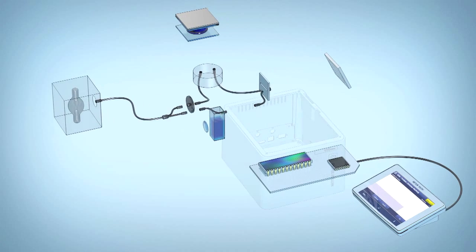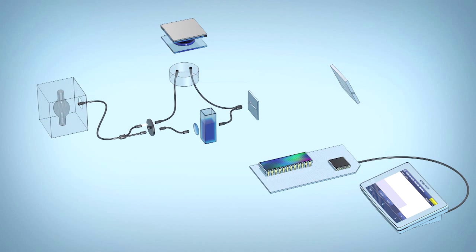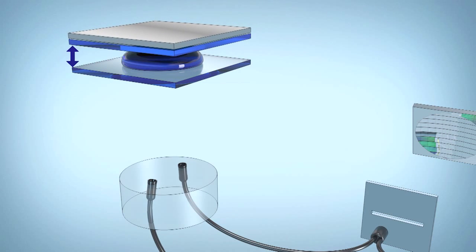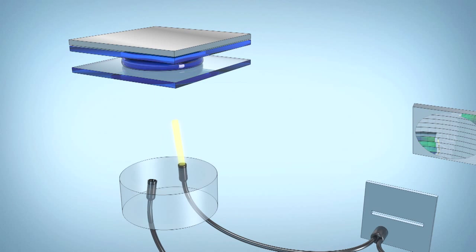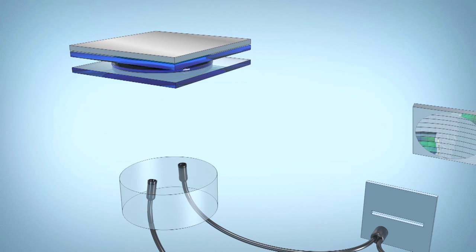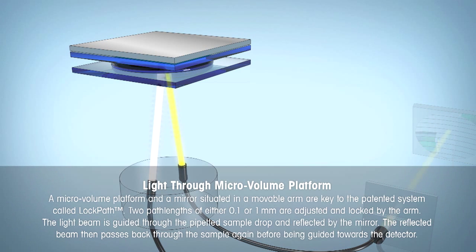The light beam is guided by a fiber to the microvolume platform. It passes through the optical cell and sample drop, is then reflected by a mirror, and then passes back through the sample before it is guided by another glass fiber towards the spectrograph.